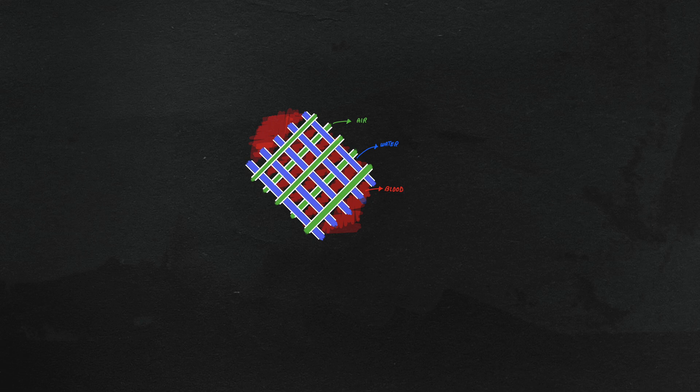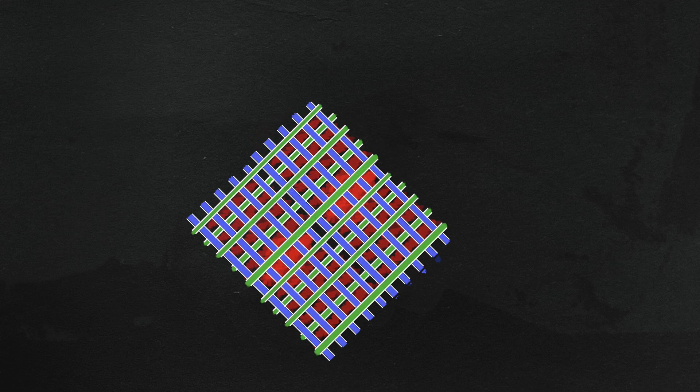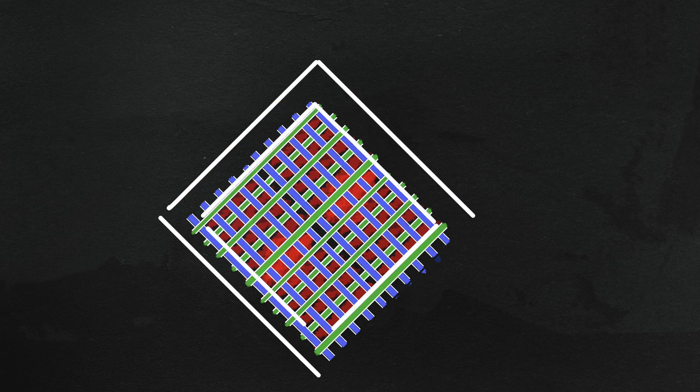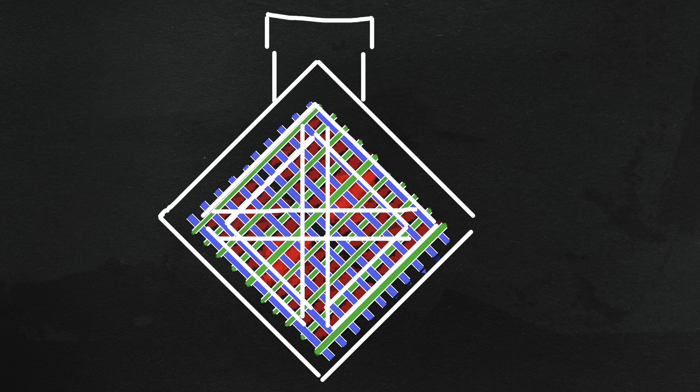The blender determines the air-oxygen mix, FiO2, and the air flow rate, called sweep. Sweep gas flow is analogous to minute ventilation or dialysate flow rate.